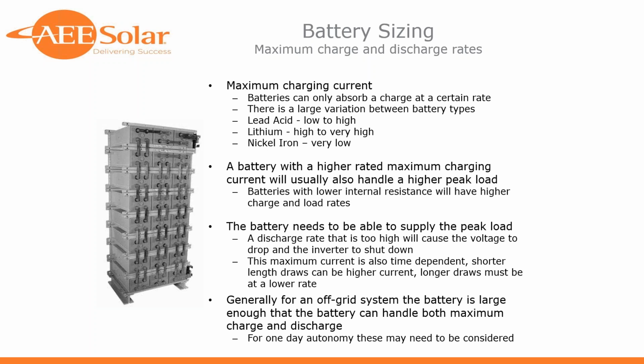And of course, it works the other way too. If you have peak loads, you need to have a battery that's able to supply that load over a short period of time. Yeah, if your application is peak load shaving or backup, right? With self-consumption, you're a little less concerned about that. Right. Yep.